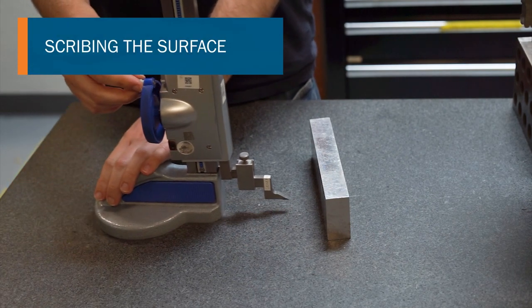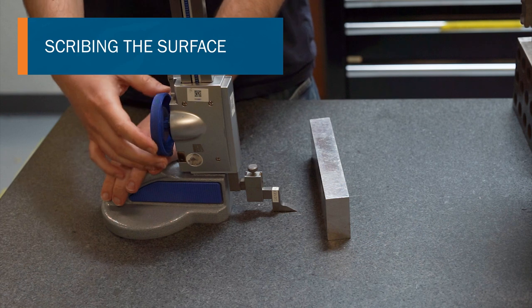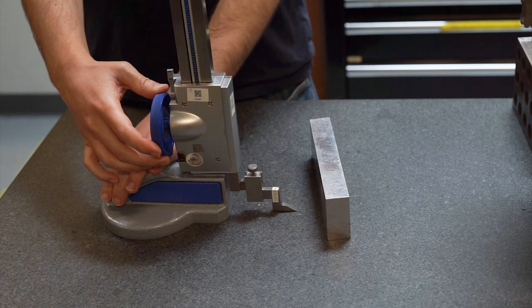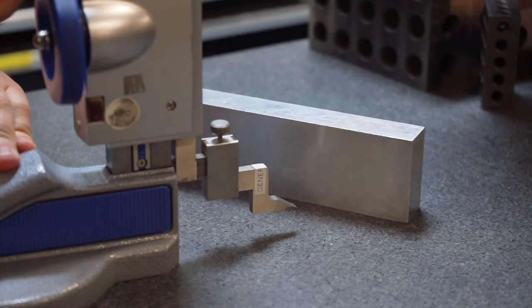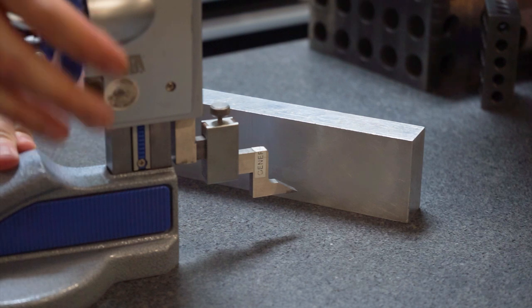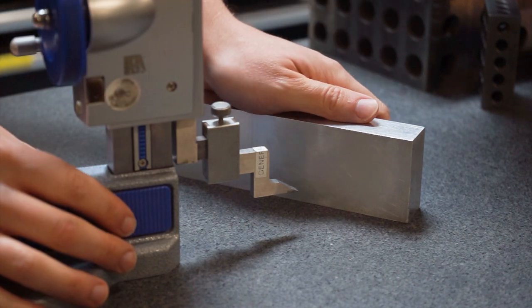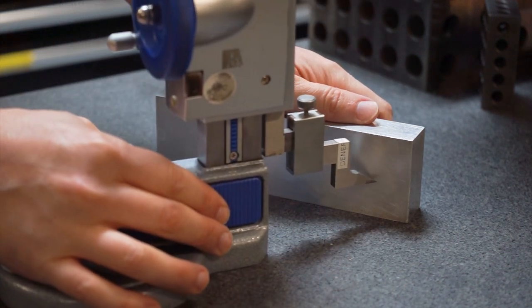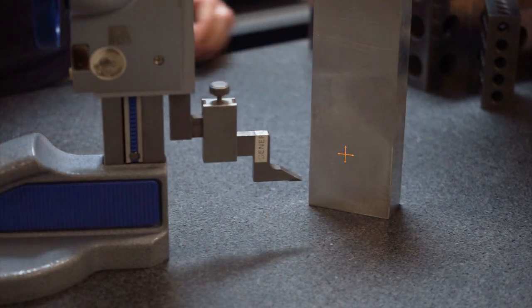Before any strain gauges can be applied, the tester must scribe the desired location for the measurement to take place. This can be done with a precision scribing tool, like this height gauge. Zero the tool on the top of the surface plate and adjust to the intended gauge location. The same must be done in the perpendicular direction to complete the crosshairs.